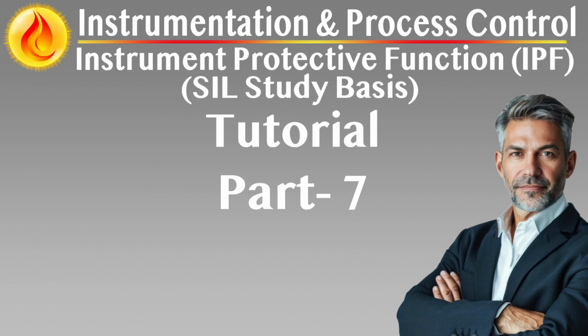Integration with maintenance and monitoring systems, event logging and reporting. All automatic test results, pass, fail, or degraded, must be recorded and made available for review. Timestamped logs support compliance audits, failure trend analysis, and proactive maintenance planning. Interfacing with asset management tools. Automatic diagnostics can feed into plant asset management systems, enabling condition-based alerts, remote troubleshooting, and predictive analytics.